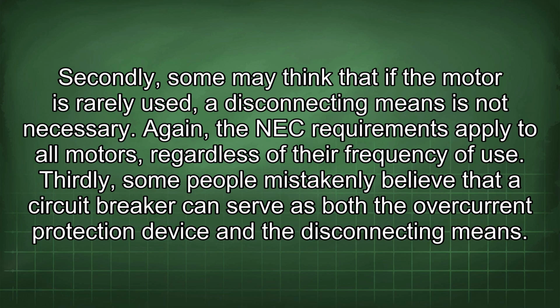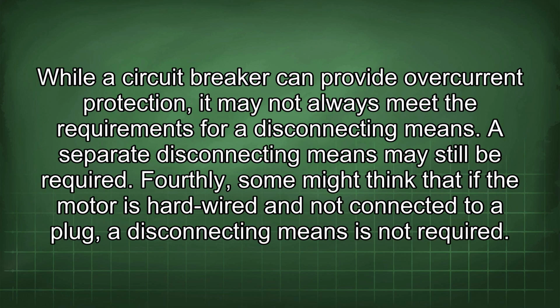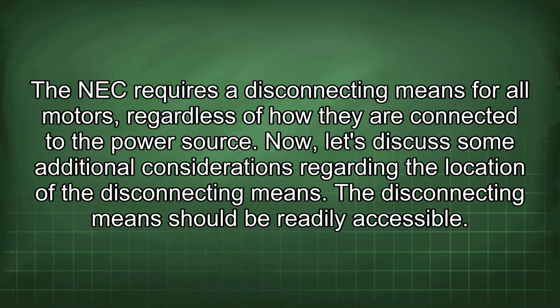Thirdly, some people mistakenly believe that a circuit breaker can serve as both the overcurrent protection device and the disconnecting means. While a circuit breaker can provide overcurrent protection, it may not always meet the requirements for a disconnecting means. A separate disconnecting means may still be required. Fourthly, some might think that if the motor is hardwired and not connected to a plug, a disconnecting means is not required. The NEC requires a disconnecting means for all motors, regardless of how they are connected to the power source.